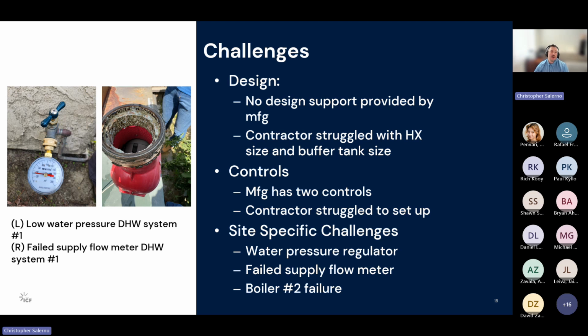And as you may know, that's a very low pressure, especially for a large central system. Typically, pressures should be ranging at least 40, 50, 60 to maintain proper flow, and then also old check valves that fail. So the low pressure was causing weird system dynamics, such as reverse flows and lines that should not have been reversed.